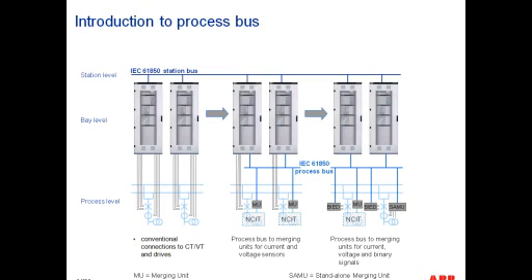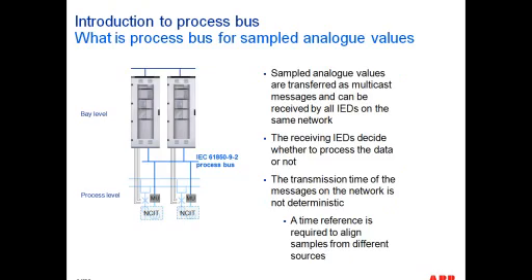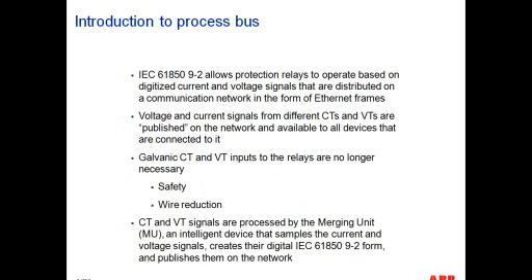a separate core to each individual relay that needs to consume that particular current signal. In the case of IEC 61850, you could use a single core associated with a merging unit, and then there is no penalty for the amount of devices that are subscribed to that sampled measured value data stream that contains that current signal. And what that allows you to do is, in a more economical manner, have more devices subscribed to current signals from a particular current transformer.